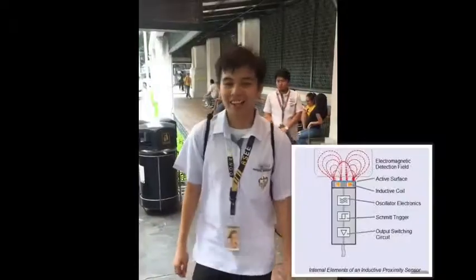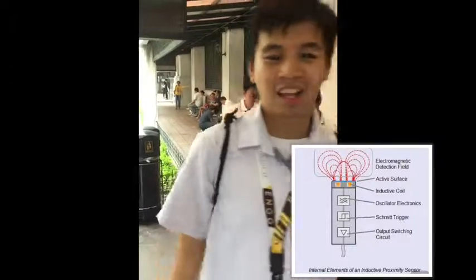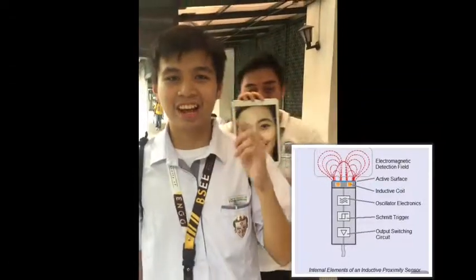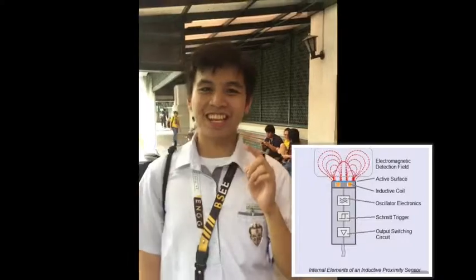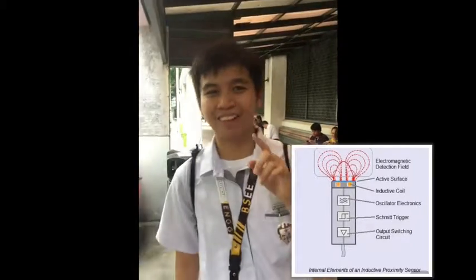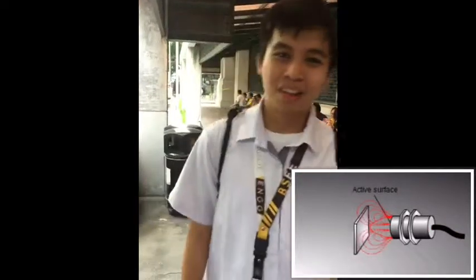One classification of proximity sensors is inductive sensors. Inductive sensors detect ferrous targets, specifically mild steel thicker than 1 millimeter. The inductive sensor has two main parts, the oscillator and an inductive coil. The oscillator energizes the inductive coil to produce an oscillating magnetic field. Once metal approaches the proximity of the magnetic field, the sensor will sense that the metal is present.